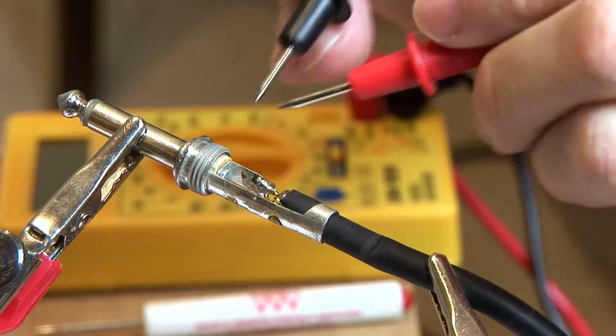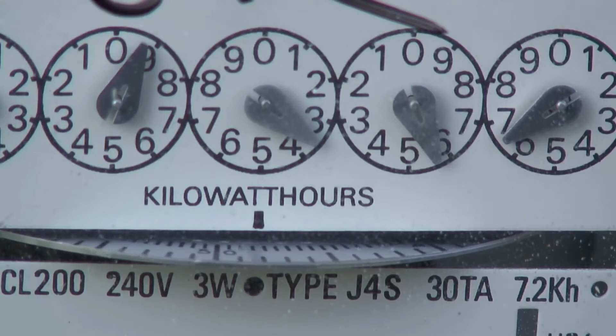Flickering lights may also be caused by fluctuating electrical voltage. There are various reasons why your home is experiencing fluctuating voltage, but most times the issue is technical in nature and points to serious faults in your electrical system. On a standard 120 volt circuit, your home should have a reading of between 115 and 125 volts. If you have a voltmeter, you can check the reading yourself. If it comes back higher than 125 volts, then that could be the reason your lights are flickering.